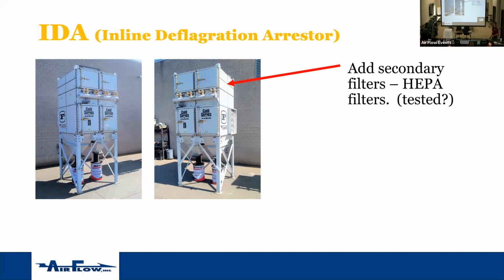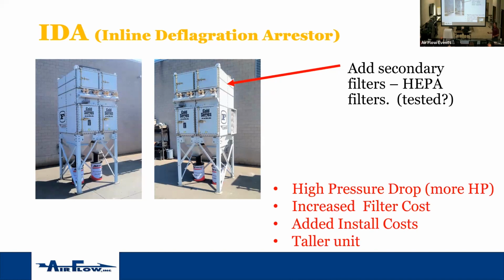A couple reasons that we don't do this: adding a second set of HEPA filters on here is a very, very high pressure drop. High pressure drop means you've got to have more horsepower. More horsepower means it's going to cost you more to run it. It is an increase in filter costs because now you're going to have to replace these on a regular basis. If you get a tear in this for some reason or blow-by, you're going to end up collecting all of it into your HEPAs. Now you've got two sets of filters that you have to replace at a pretty hefty cost. It also adds installation costs because this whole module will come and you'll have to bolt that on and install the filters in it, and it creates a much, much taller unit for service. So now if you're only talking about putting a platform here to access this, now you've got a platform that someone's got to put a step ladder on to access the HEPA filters.